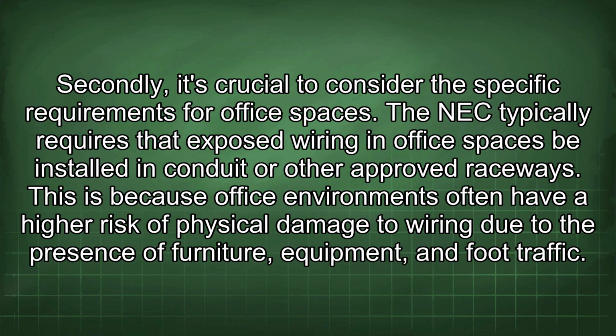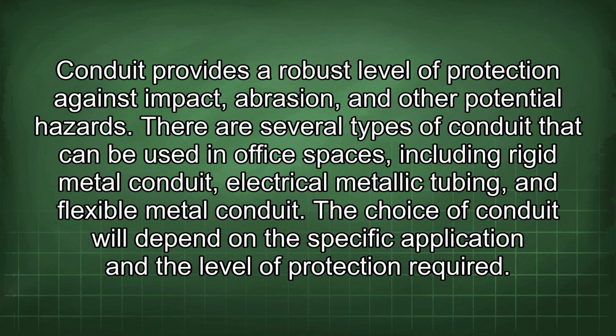Secondly, it's crucial to consider the specific requirements for office spaces. The NEC typically requires that exposed wiring in office spaces be installed in conduit or other approved raceways. This is because office environments often have a higher risk of physical damage to wiring due to the presence of furniture, equipment, and foot traffic. Conduit provides a robust level of protection against impact, abrasion, and other potential hazards.